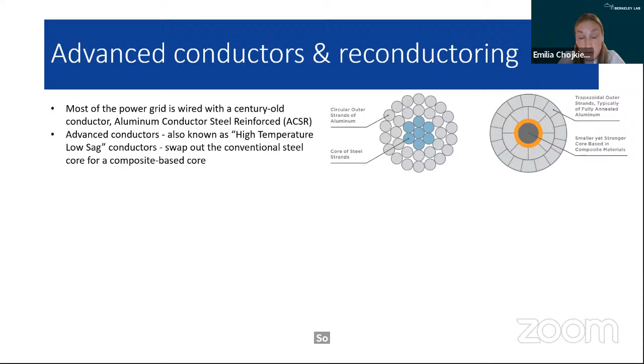What is an advanced conductor? Basically, most of the US power grid and power grids around the world have been wired with a century-old conductor called aluminum conductor steel reinforced, or ACSR. What an advanced conductor does is swap out that conventional steel core for a composite-based core. On the left you see the traditional conductor, and on the right the advanced conductor with the composite core and trapezoidal rather than circular strands.